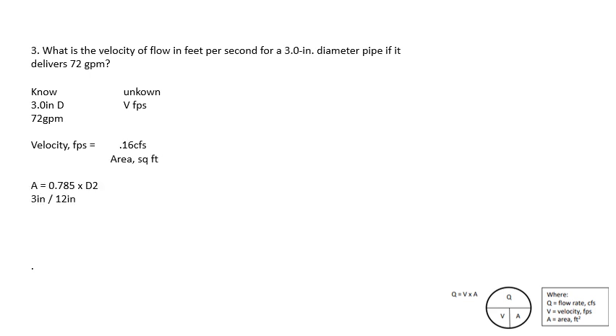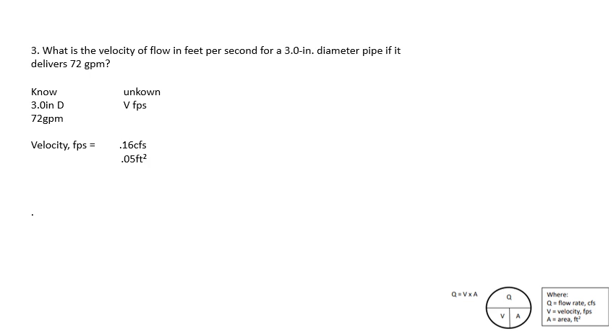Plug 0.16 cubic feet per second into the formula. Now solve for area in square feet: 0.785 times diameter squared. Convert 3 inches to feet by dividing by 12, giving 0.25 feet. So area equals 0.785 times 0.25 squared, which equals 0.05 square feet. Then 0.16 divided by 0.05 gives an answer of 3.2 feet per second.